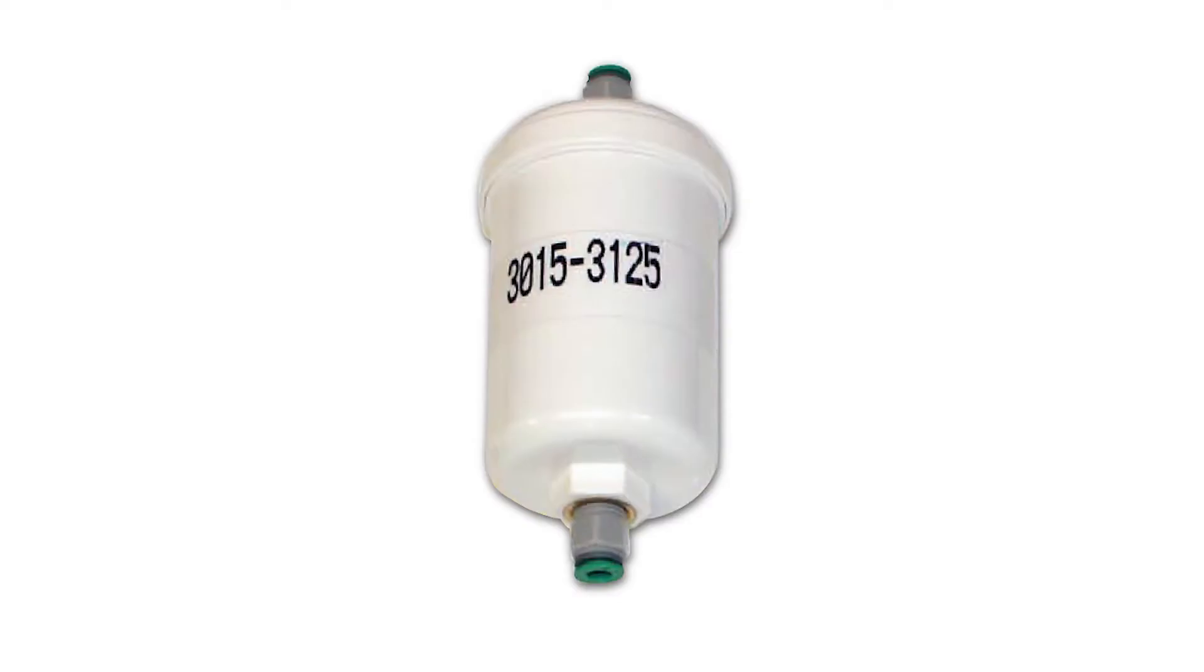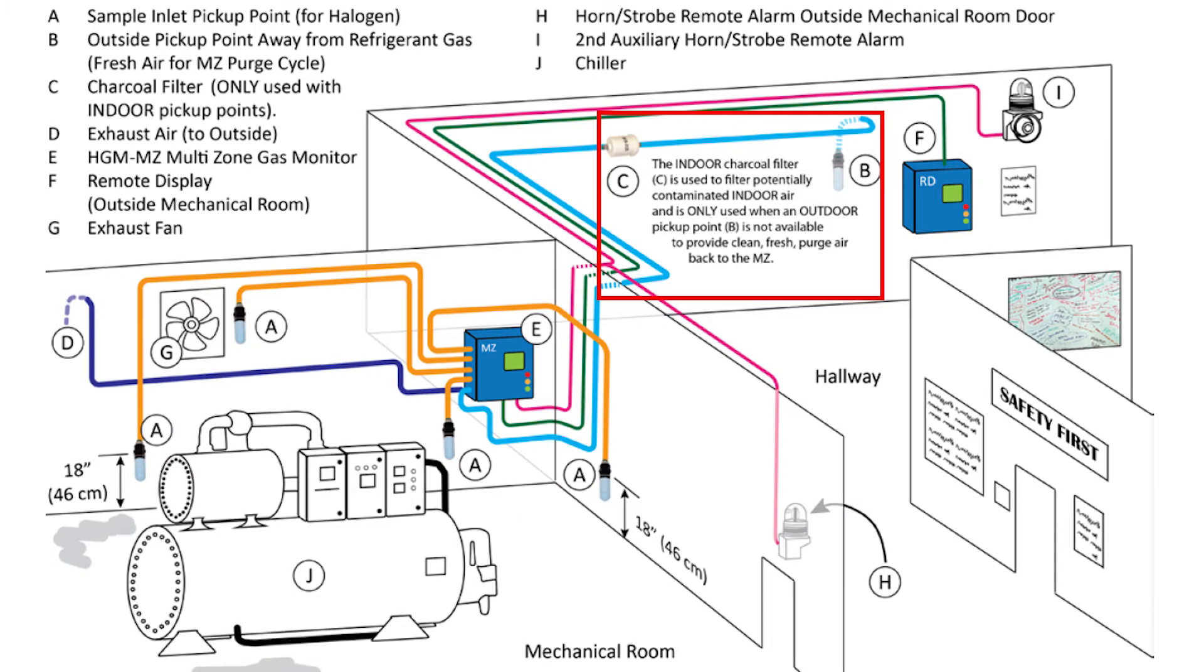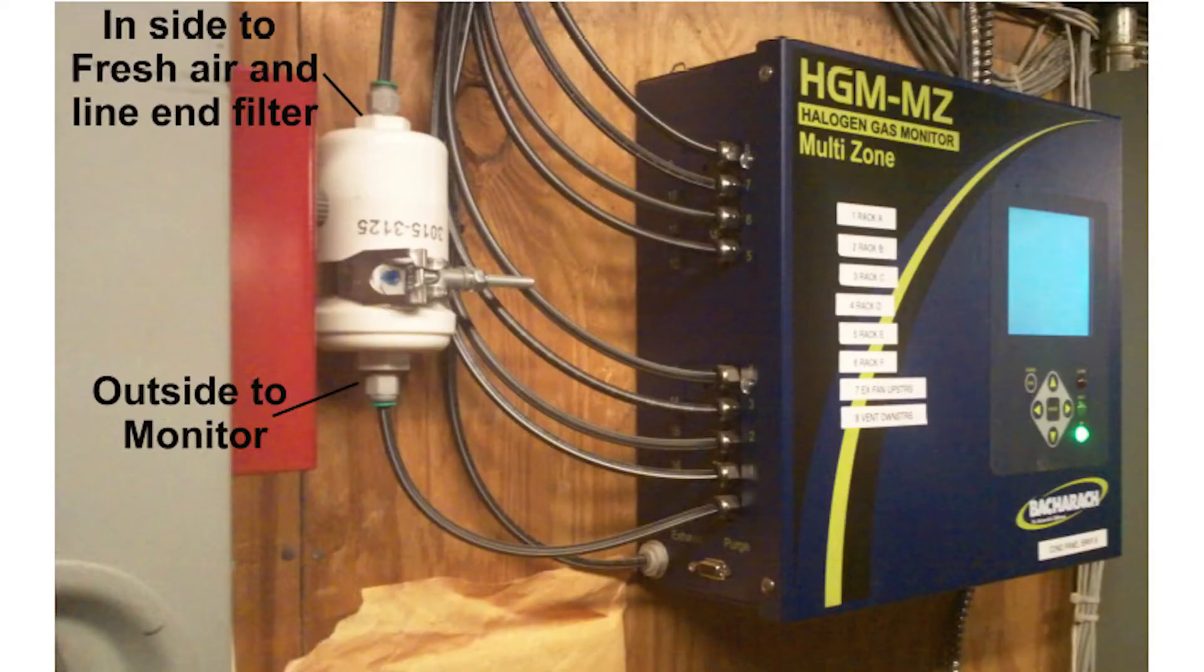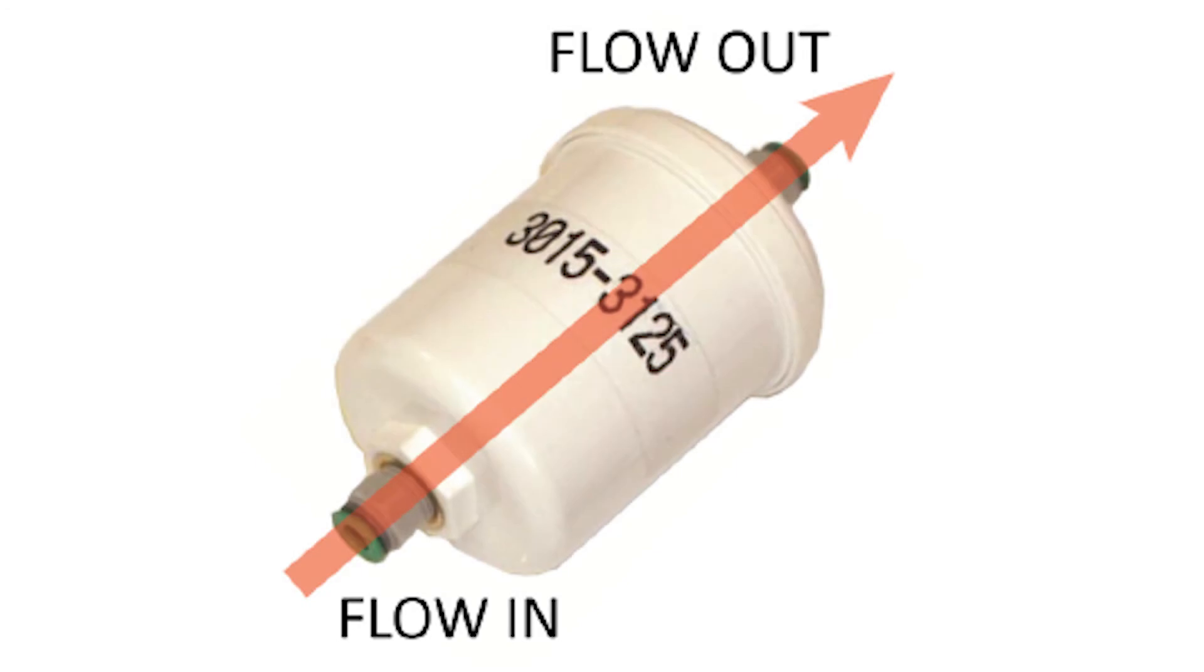The charcoal purge filter, which will be integral to purging contaminants from the monitor, should be mounted outside of the mechanical room where air samples will be taken and away from any potential contaminants that could interfere with the system. It is recommended that the charcoal filter is placed near the monitor so it is easily accessible for maintenance and replacement. Use tubing to connect the outside of the charcoal purge filter to the purge port on the monitor.